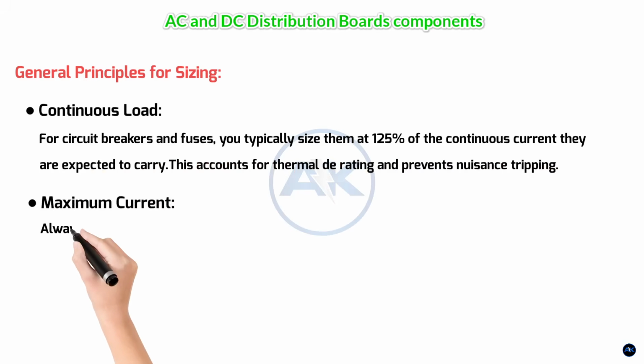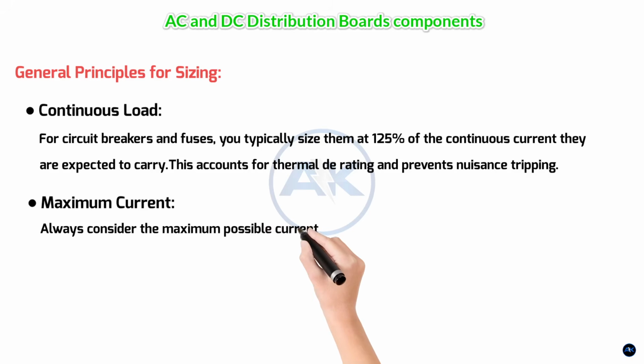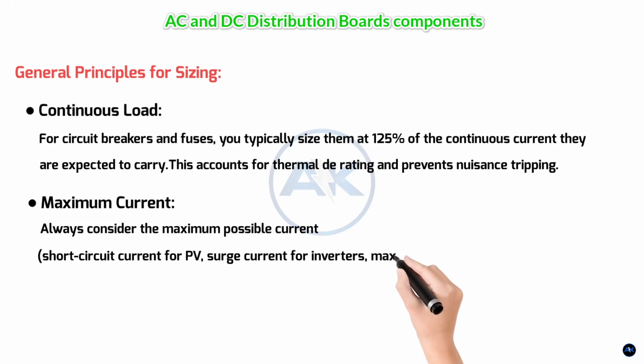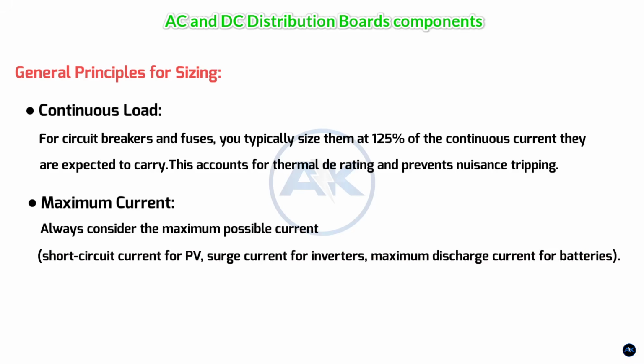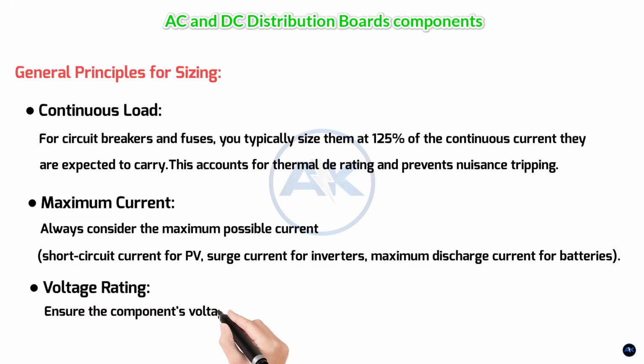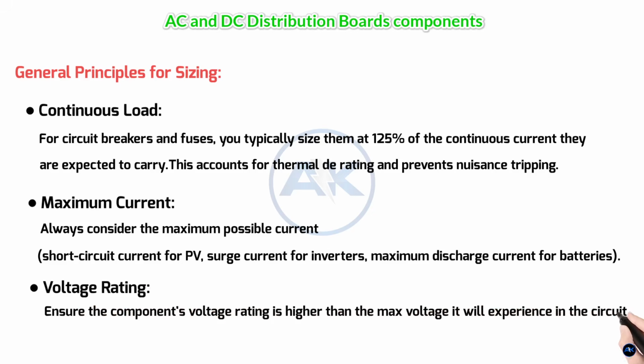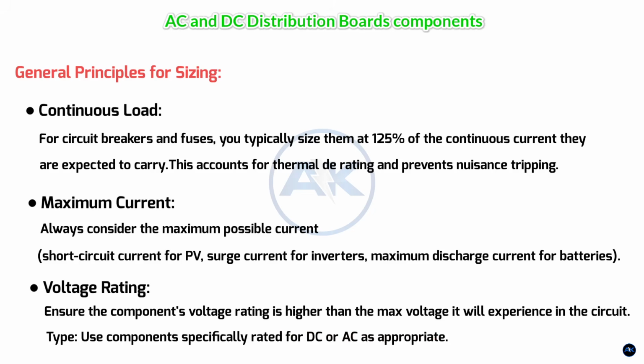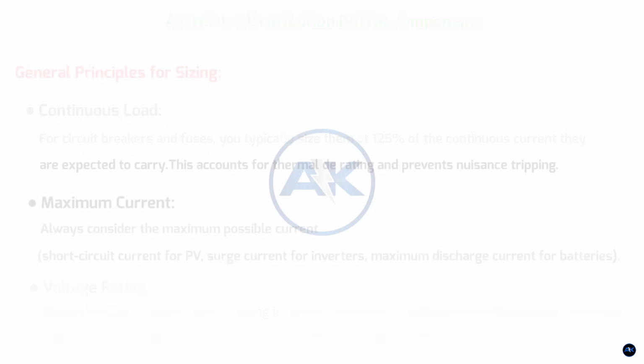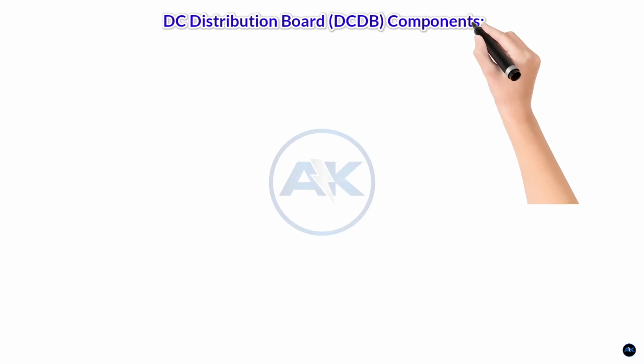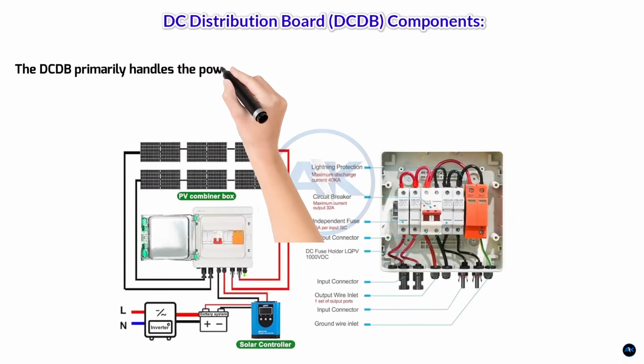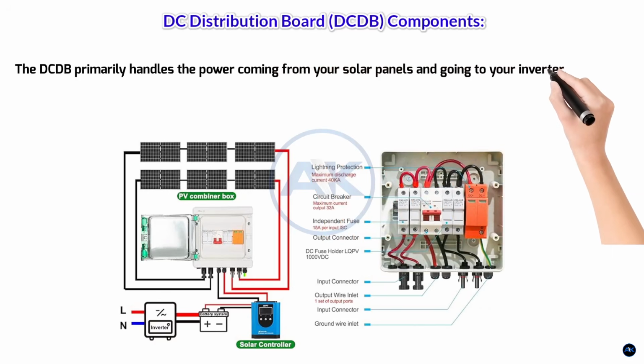Maximum current. Always consider the maximum possible current: short circuit current for PV, surge current for inverters, maximum discharge current for batteries. Voltage rating. Ensure the component's voltage rating is higher than the maximum voltage it will experience in the circuit. Type. Use components specifically rated for DC or AC as appropriate. DC distribution board, DCDB, components. The DCDB primarily handles the power coming from your solar panels and going to your inverter.